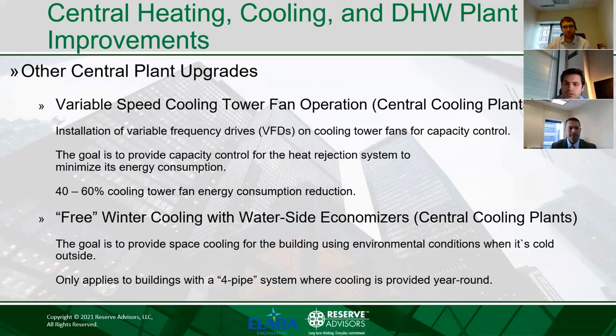Two types of projects, for instance, here in the slides, require lower capital investment and usually do not involve large construction disturbance. As mentioned earlier, water-cooled central cooling plants use a cooling tower to reject heat absorbed during the air conditioning process. From an energy efficiency perspective, one low-hanging fruit for cooling towers is installing variable frequency drives, or VFDs, on cooling tower fans. This is a very simple project. The goal here is to provide capacity control for the heat rejection system to minimize fan energy consumption during low load conditions.